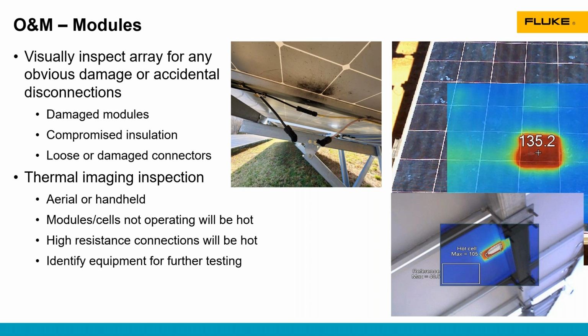Any part of the module that is not operating will be at a higher temperature than the section of the module that is operating. And that's because when a cell's not operating or under load, the electrons are still being excited by the sun. They have nowhere to go, so they're dispersing some of their energy as heat, and that's what you're able to pick up on the thermal camera. But as I mentioned earlier, the system has to be under a pretty high level of load in order to get a good quality thermal image.